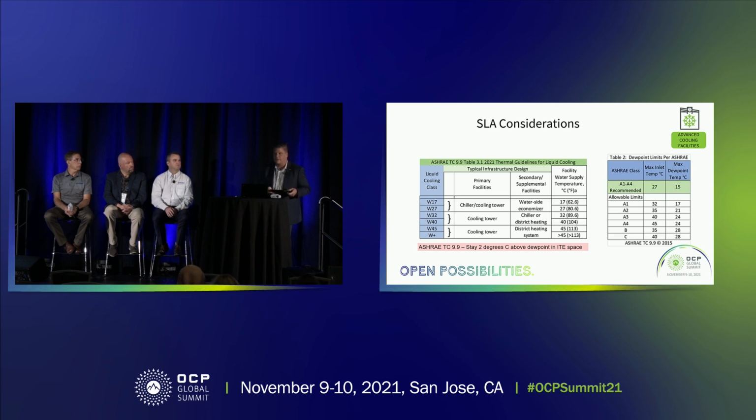So a couple things real quick, and we do have to leave. Number one, what ASHRAE does is what ASHRAE does, and we reflect that. So what you're bringing up is, to a large extent, something that ASHRAE should make the recommendation on, and we're never going to go back to ASHRAE and tell them how to do their job. Number two, I would like to highlight that ASHRAE's current recommendation for dew point is about 15 degrees centigrade for the recommended regions. As far as I know, is that correct?